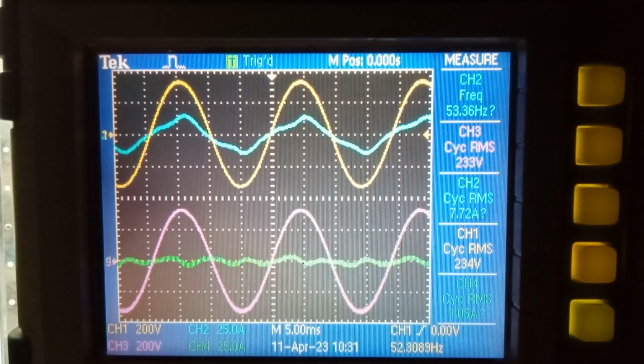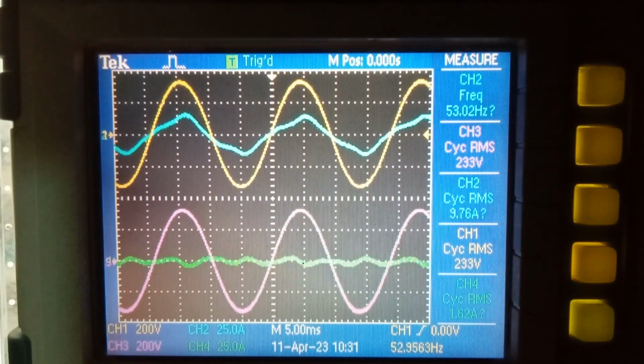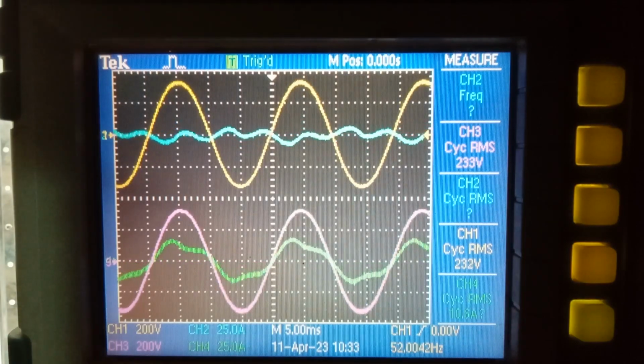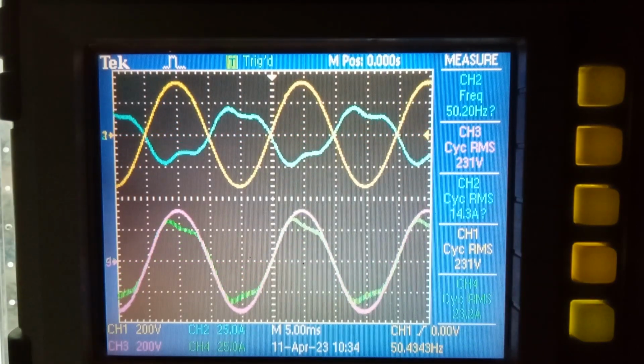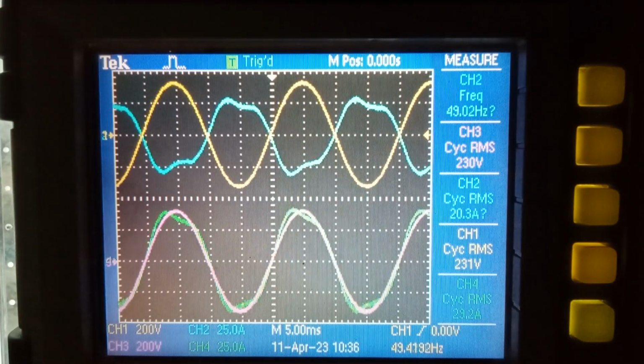Okay, the inverter is pulling the generator voltage into a good sine wave, so it's causing some third harmonic current to flow. The generator current will ramp up over the next 5 minutes and warm the generator up. Okay, now you can see 30 amps coming out of the generator and about 20 amps going backwards through the inverter into the batteries. Plus we have another 10 amps going into our 2 kilowatt load.